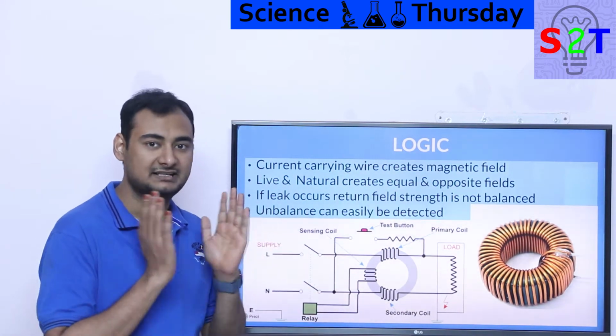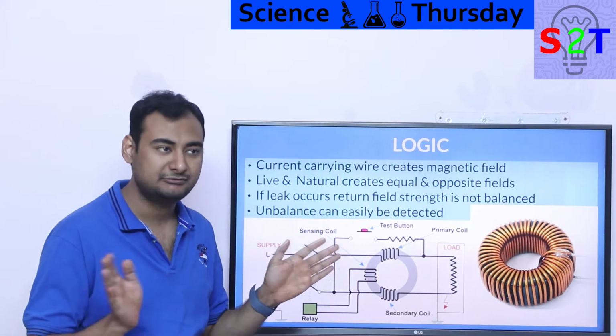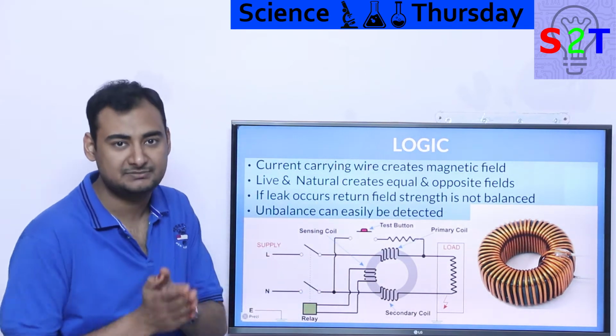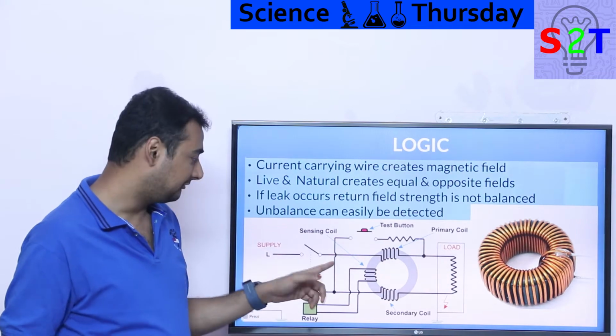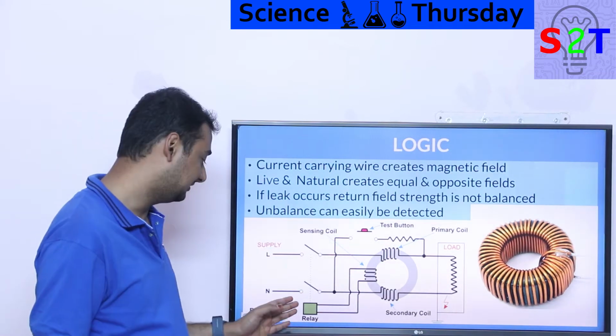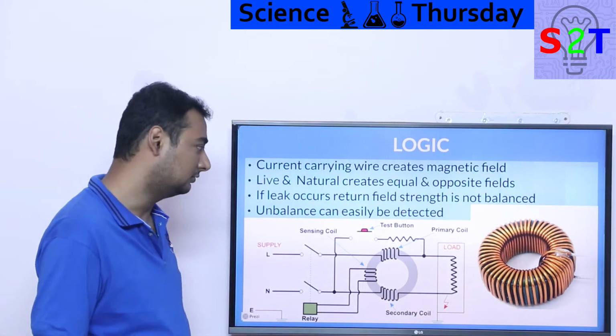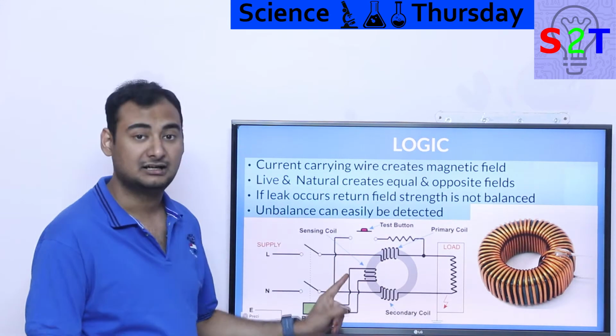You have a toroid, you have basically a transformer that is completely in an off state. If everything is going well, it's in the off state. The moment there is an unbalance between live and neutral, it fires the third coil, and the third coil energizes the relay, which cuts the connection. That's the whole thing. All you are doing is detecting an unbalanced state.